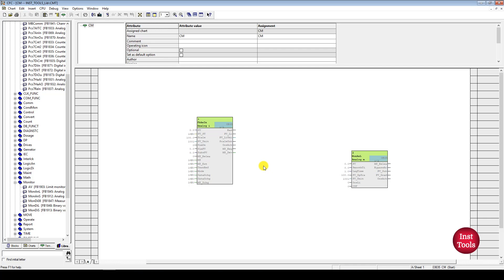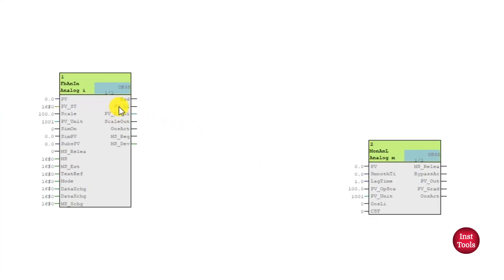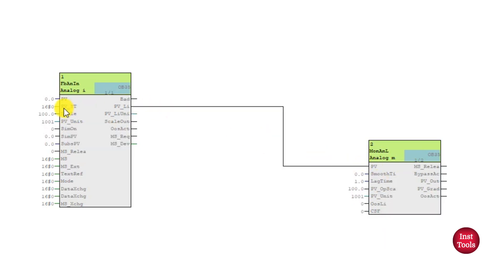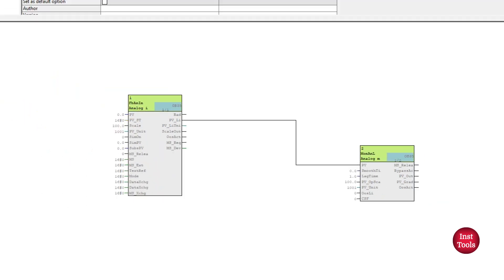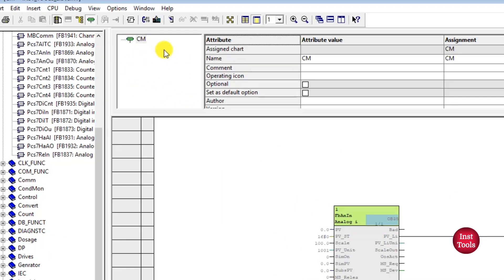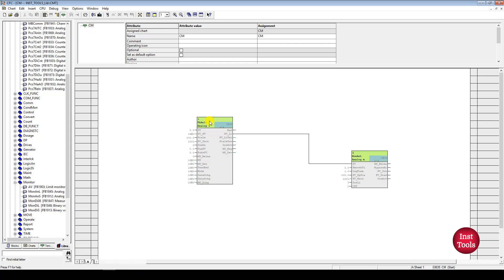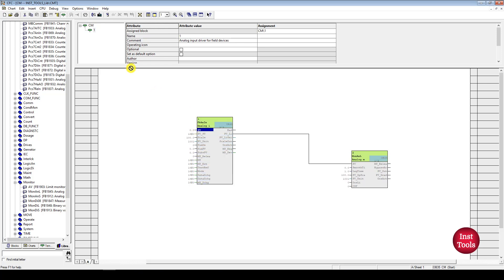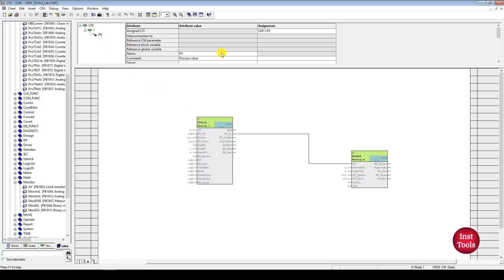Here I can make interconnections manually — linking PV to PV. The interconnection is made between the blocks. In order to connect to global addresses or charts outside the project, we need to connect the blocks to the tech level. This white area is termed as the technological level. I will drag this block to the tech level, and drag the relevant pins to the tech level as well.